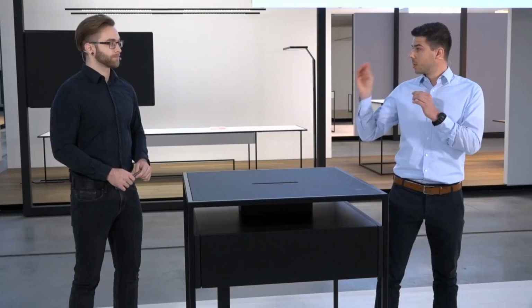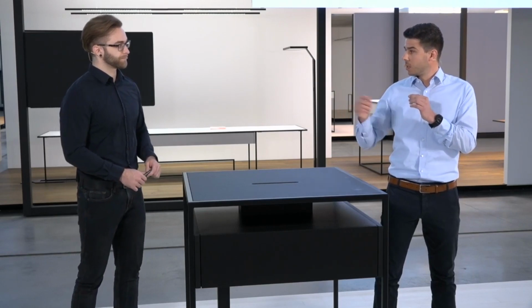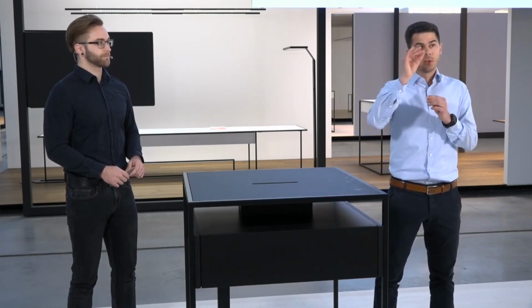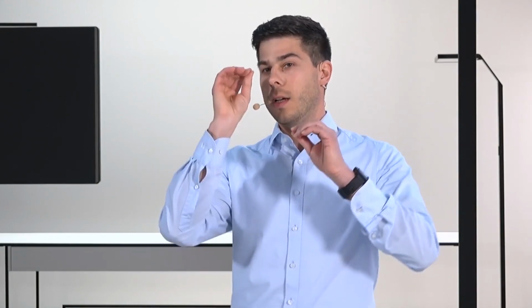So for example, you could keep your normal lighting, scenes, and sensors in the Basic Dim wireless system, and only pick and choose the emergency wireless luminaires to be translated to the DALI line. This DALI line is then connected to a SceneCom controller.